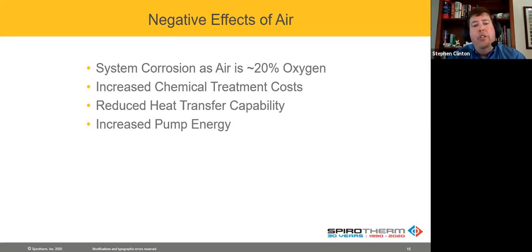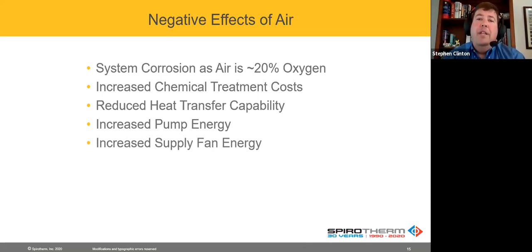The other thing is you increase the pump energy. Why is that? Well, we're going to show you some documents in just a second, a few slides down, that talk about that. But essentially what's happening is the pump is only designed to pump water. It's not designed to pump water and compress air at the same time. That's really what it's doing. It's not made for that. Now, why would this be the case? Well, think about it this way, especially those of us in the South or other places where we deal with humidity all the time. If I'm trying to get 52-degree discharge air temperature off of a coil, but let's say I have air in the coil, and I'm only getting 60 degrees, well, I need to account for that heat transfer. What do I do? I have to increase the supply fan energy. It's a heat balance. So inefficiency on the water side affects the air side. Supply fan energy is much less efficient than pumping energy.